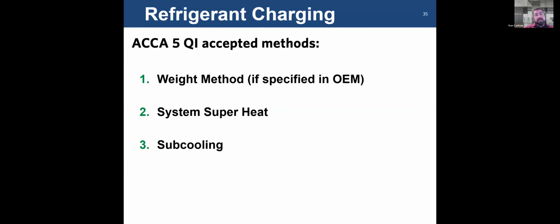Per ACCA 5, and even in the industry for that matter, there are three methods to add refrigerant. You can weigh it in, you can do superheat, and you can do subcooling. Most mini splits, and heat pumps for that matter, want you to weigh it in. They don't want you doing superheat or subcooling. They want a certain amount of refrigerant charge based on how much piping you have and the outdoor unit. What the unit comes pre-charged with is posted on the unit. If you need to add more refrigerant due to more line set being added above whatever it's pre-charged with, you would have to weigh it in.